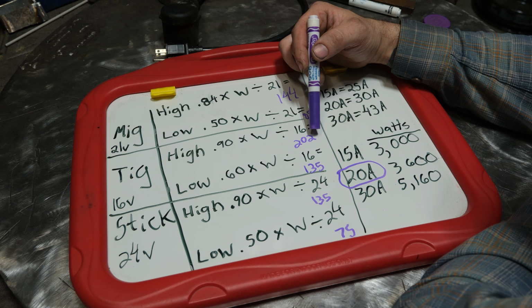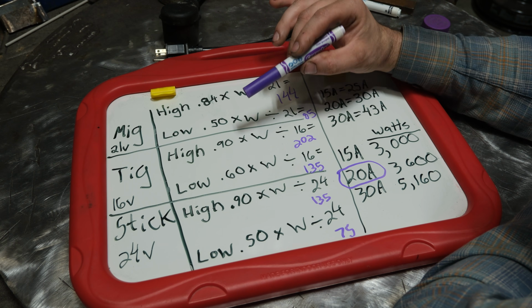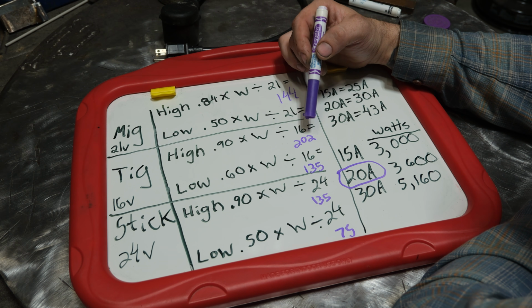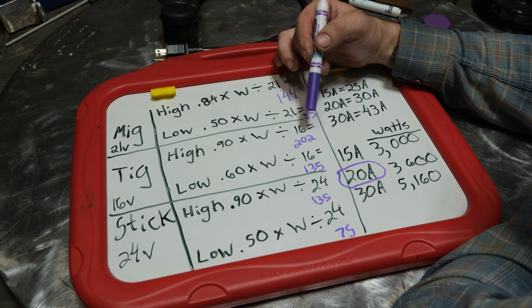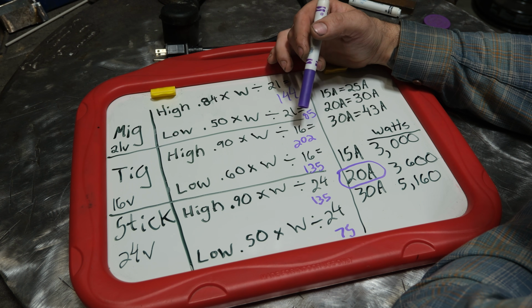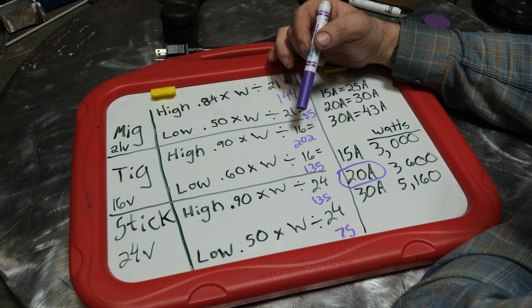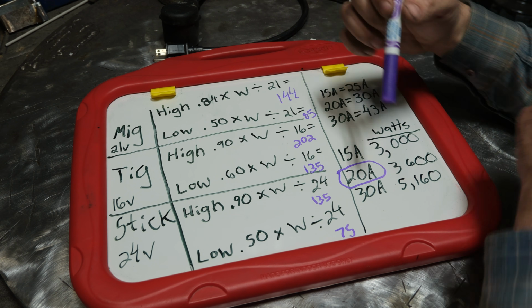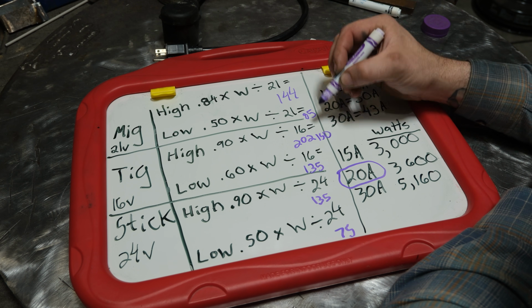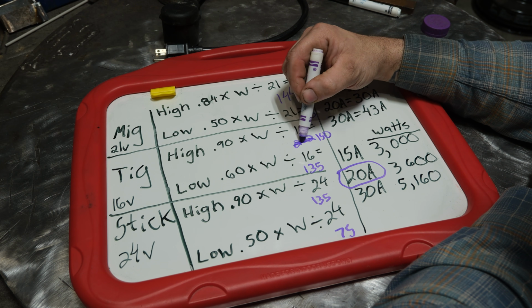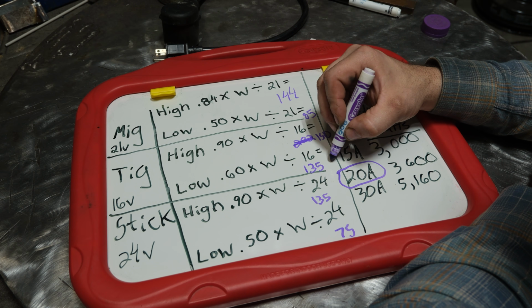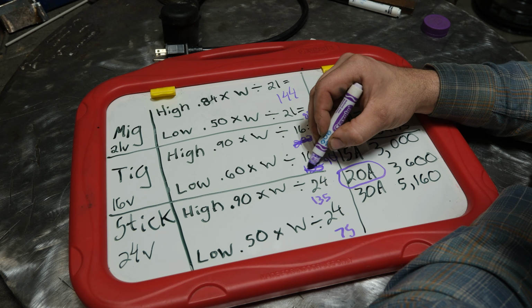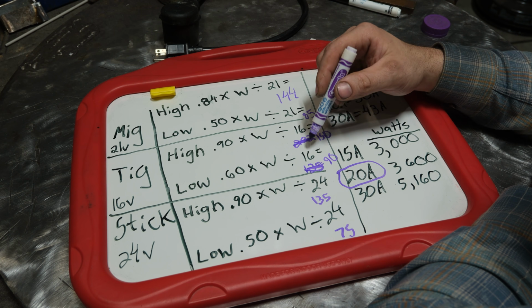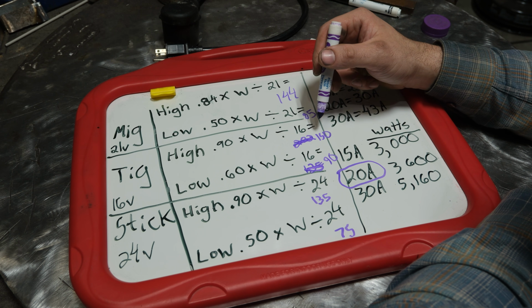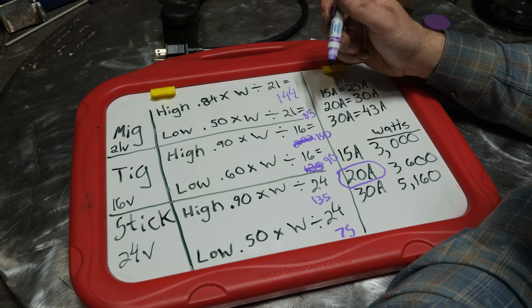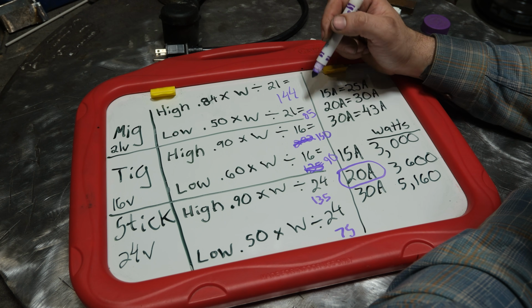Now most 120 volt capable TIG machines that are highly efficient are about 140 to 150 amps. And that's simply because variations in arc gap length would easily trip the breaker if you go above about 150. So most machines limit themselves to less than that to prevent nuisance breaker trips. So a more realistic number with TIG is somewhere around 150 amps, absolute maximum, instead of 200. And then on a low efficiency machine, somewhere around 90 to 100 amps. Again, the formula is not wrong. It's just that most of the TIG machines limit themselves to prevent nuisance breaker trips. More or less, the arc cuts out before you pull enough amperage to trip the breaker. So that is more realistic.